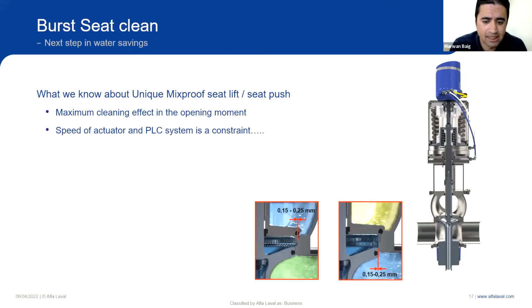Without going into further detail, each time we clean these valves we lose a lot of water since it goes down the drain. The moment we trigger the signal for a seat clean through a PLC for a valve seat lift, the first half a second - depending on the size of the valve - is when the fluid cleans the seal most effectively, as it is turbulent flow at that time. The time from the PLC to the valve has basically been a bottleneck, as it has been difficult to control.